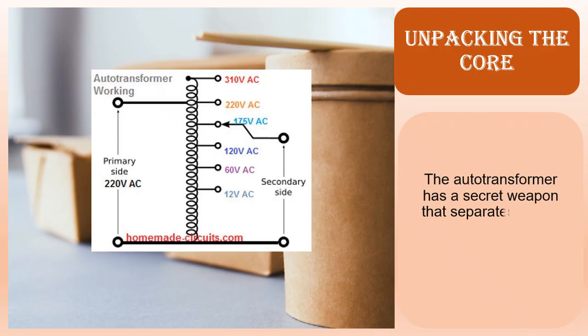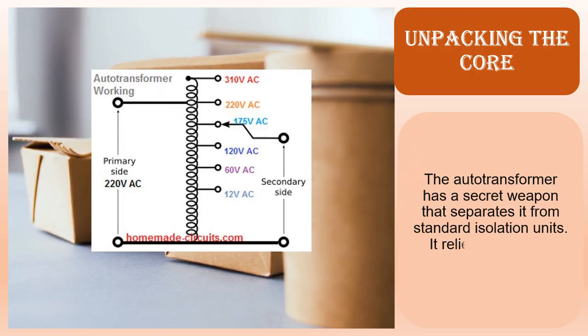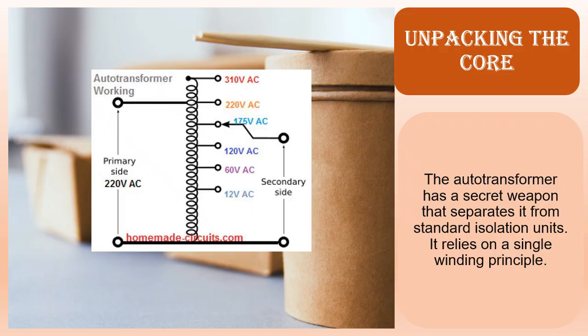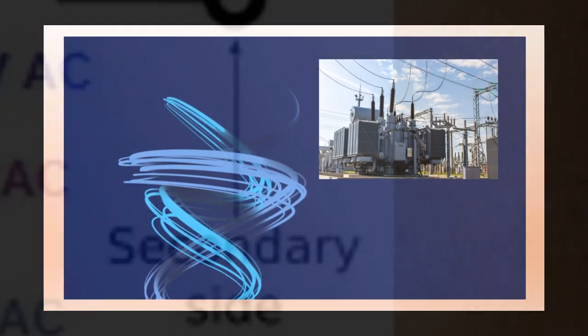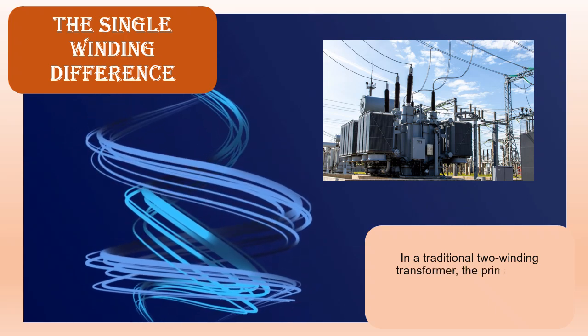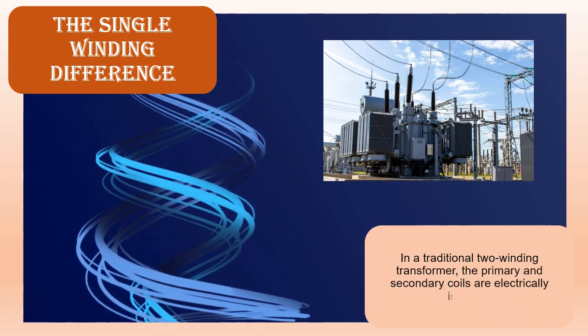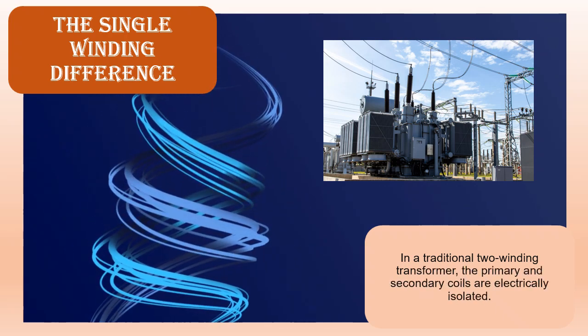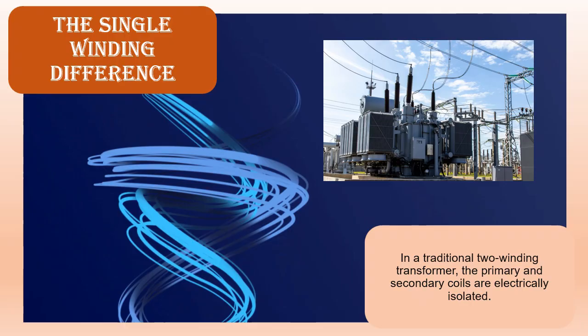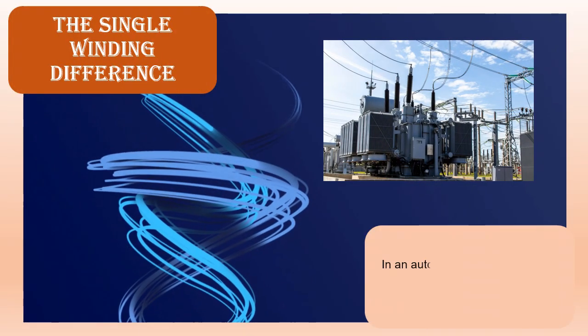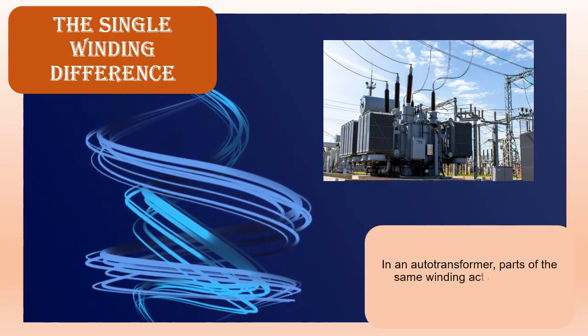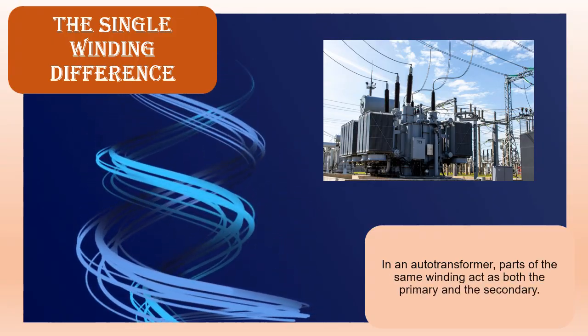The single winding difference. In a traditional two-winding transformer, the primary and secondary coils are electrically isolated. In an autotransformer, parts of the same winding act as both the primary and the secondary. The tapping mechanism. It works by tapping into different points along that single coil. The input voltage is applied across the entire winding, while the load is connected to a tapped section.